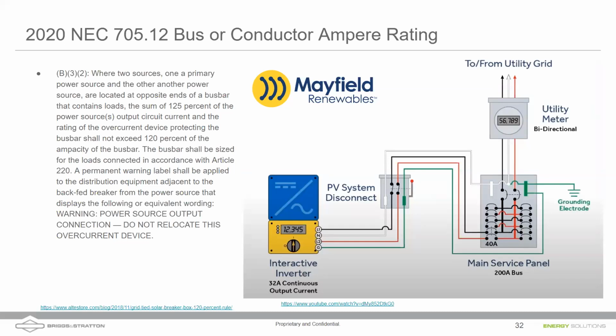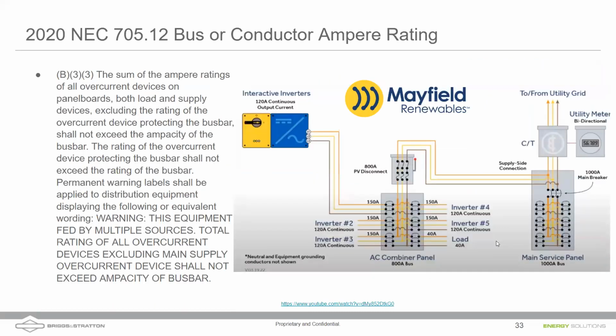A lot of times there are center fed mains on panels. We're not going to get into that, but the idea is that if you're sending power in from one end of the panel and from the opposite end, it's not going to create a hot spot, or it's going to first supply power to any loads that are on in the home at that moment before being backfed. So you've got to put a sticker on there.